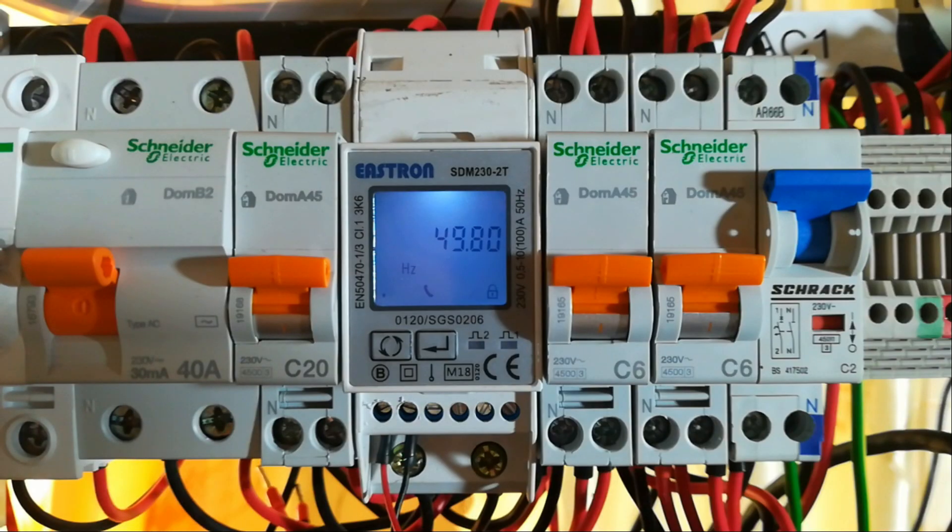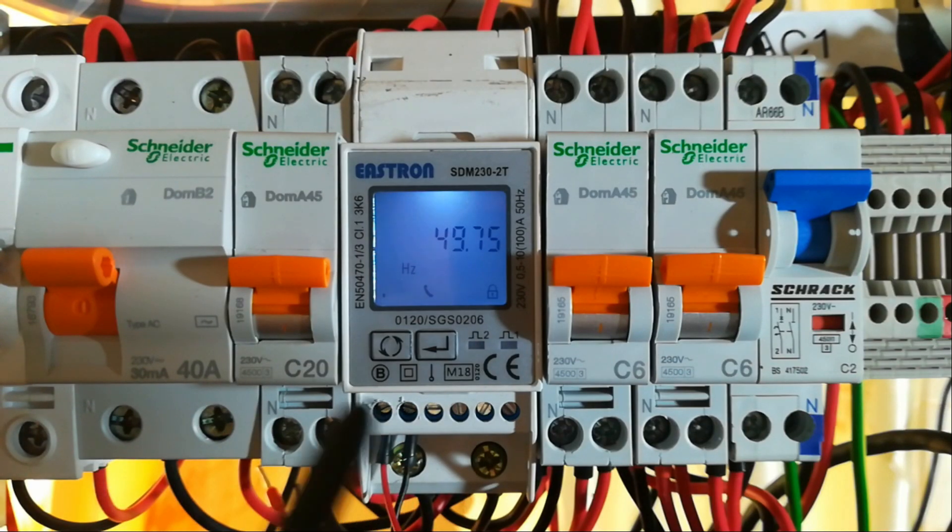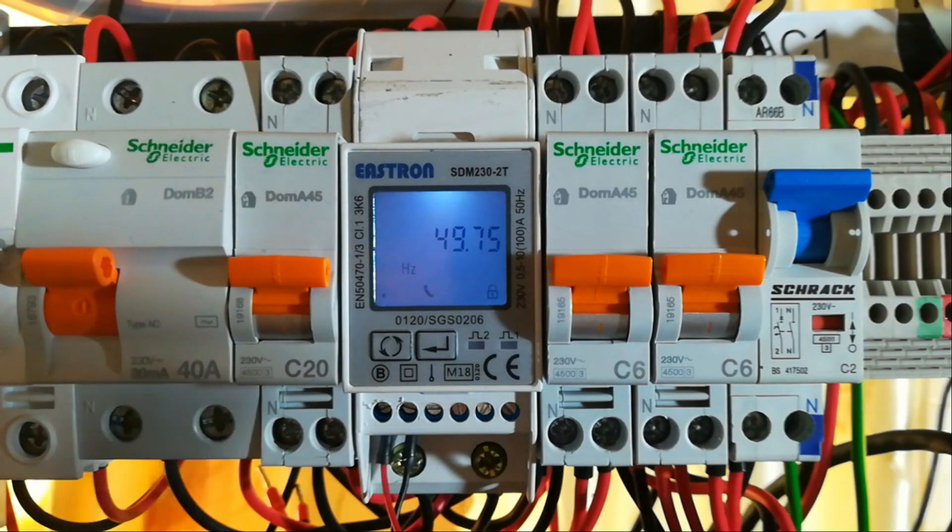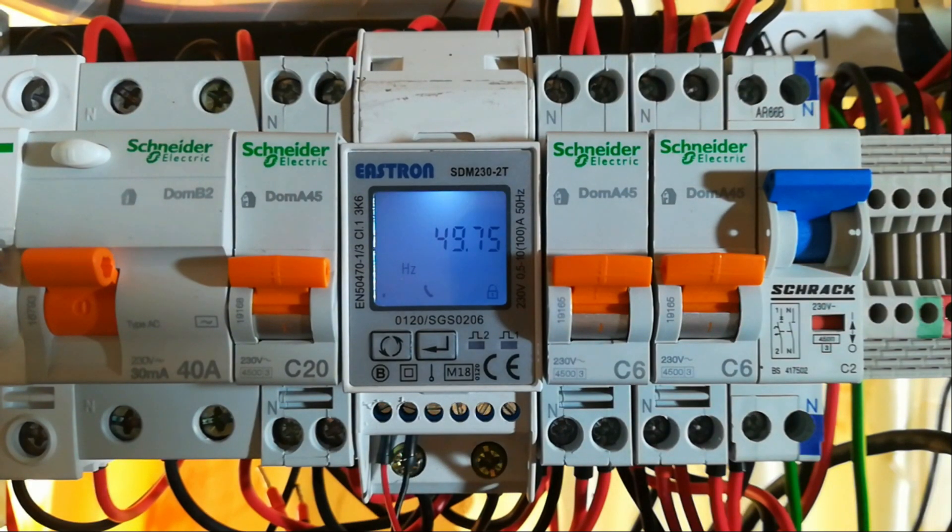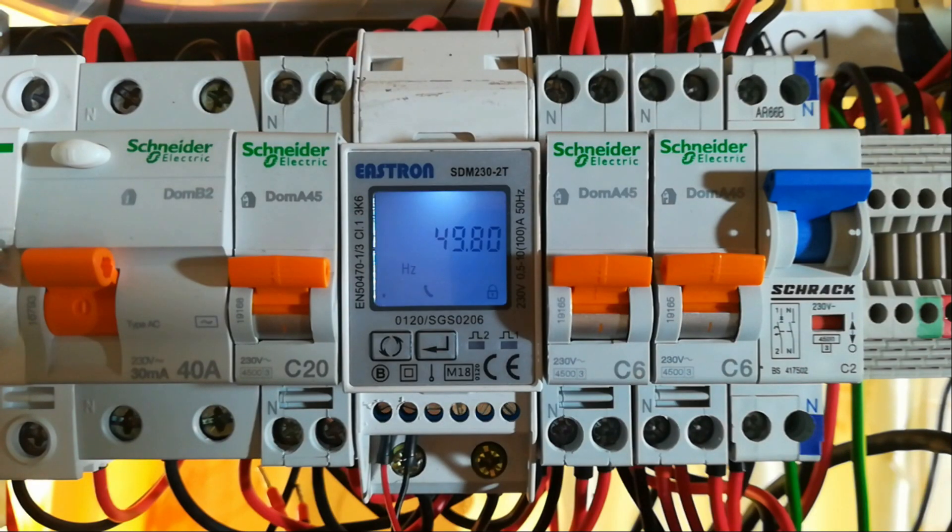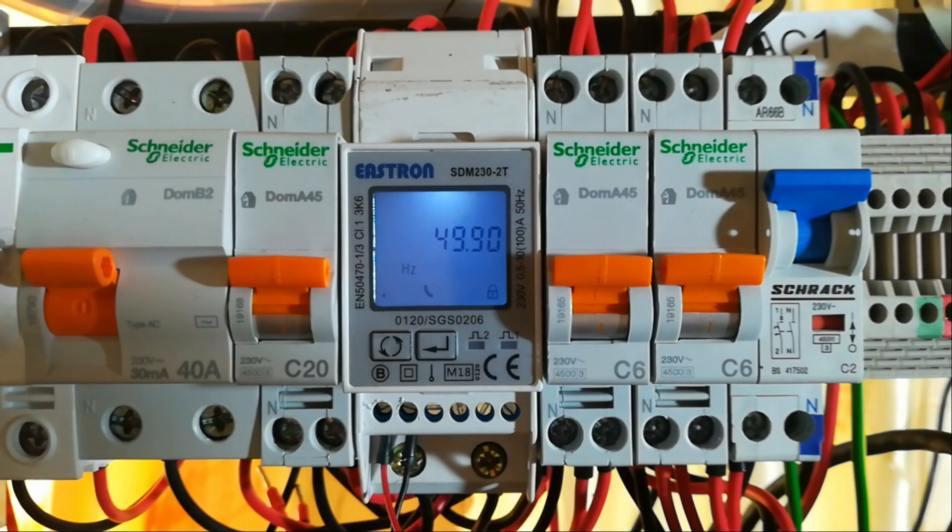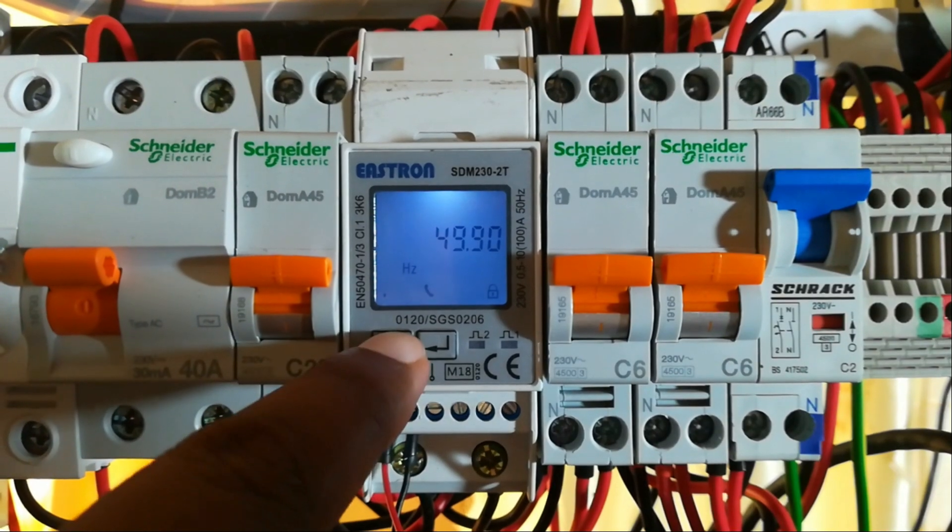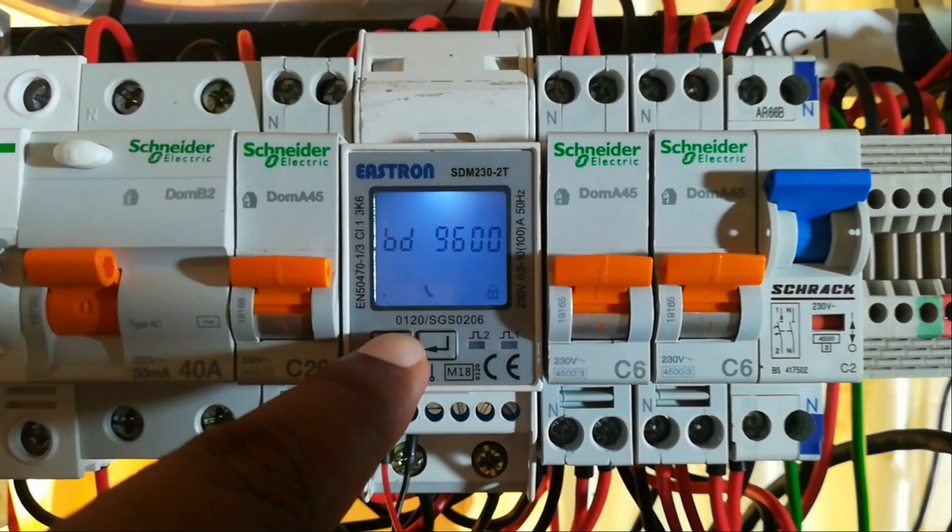For the communication you have two wires, that is the red and the black, and this is the 485 MODBUS A plus and the B minus. By connecting these two wires we can have the communication from a device to a master device, that is a master can be a SCADA or an HMI. I will just scroll across the window to show you the different parameters.